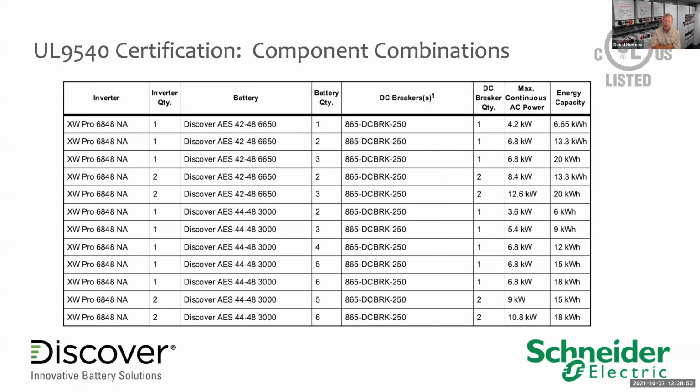And it's a public PGM and Modbus map too, right? So as long as you're familiar with that stuff, the hooks are in. Exactly. You will need a Modbus master to read and write to the individual registers, but a lot of OEMs are doing that. But as David mentioned, XanBus is a proprietary network, so there won't be any direct communication. That's handled by converting to TCP over IP through the edge devices Jack mentioned, which is Insight Local.